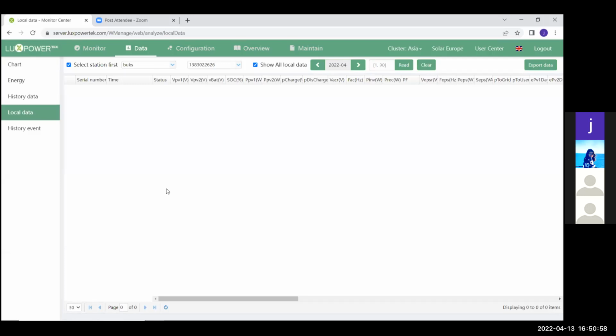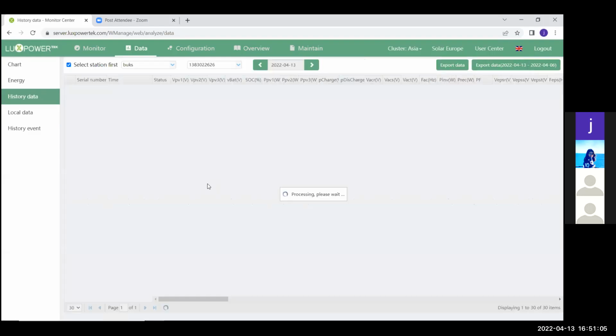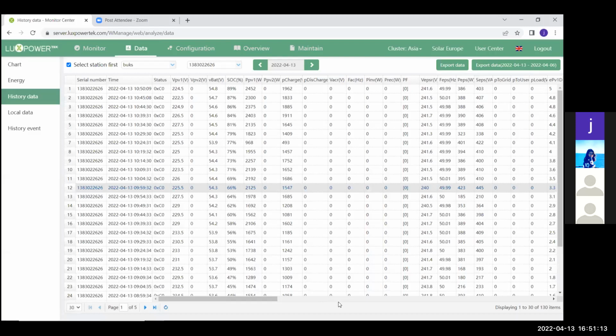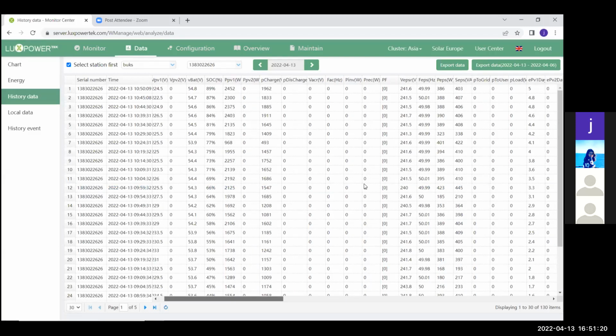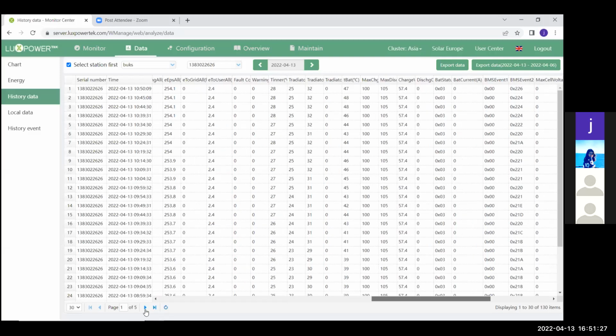This one to quickly load. Then I can also show you at this moment where the inverter and the communication is happening. So if you go to your data source, history data, then you can go all the way. Just looking for that tab here. Okay, max charge. You see this max charge here.